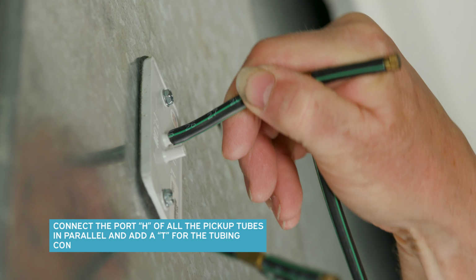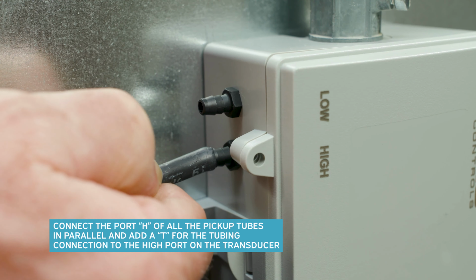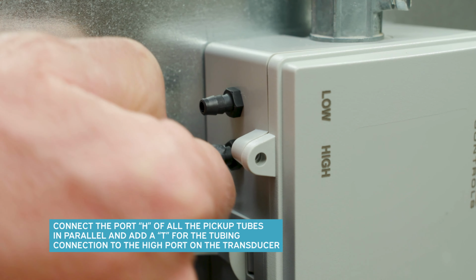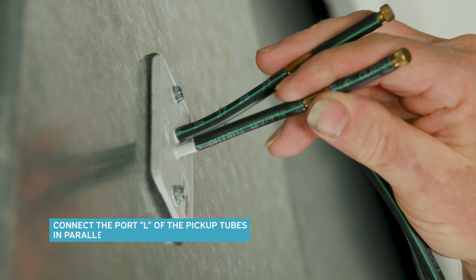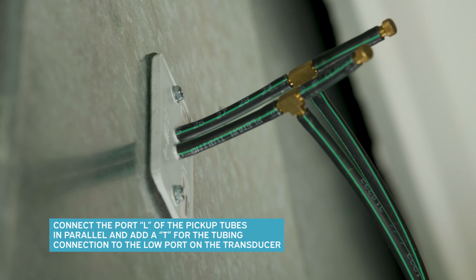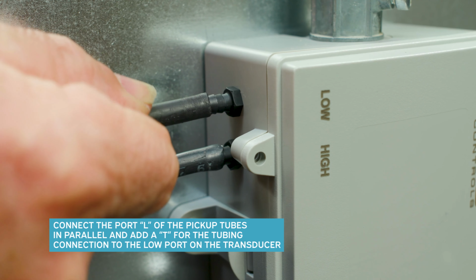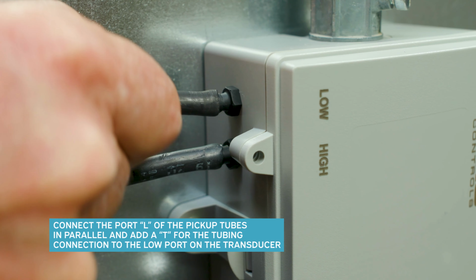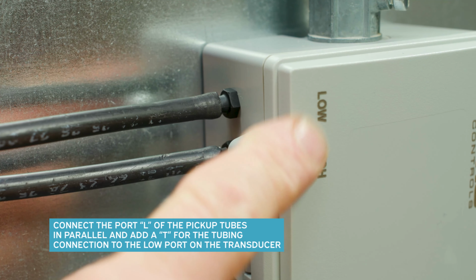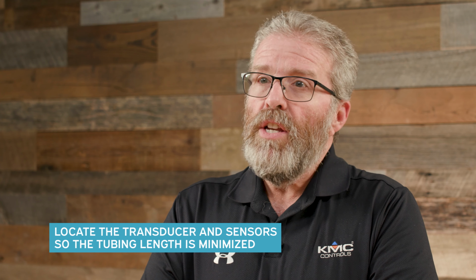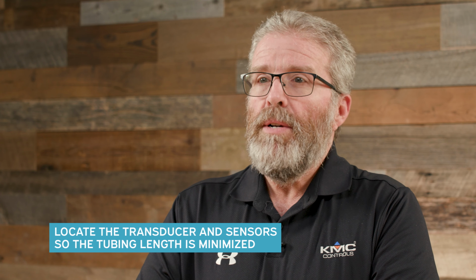Now that the transducer is installed, connect the port H's of all the pickup tubes in parallel and add a T for tubing connection to the high port on a supply air pressure transducer. It is best practice to locate this T in the middle of the manifold. Next, connect the port L's of all the pickup tubes in parallel and add a T for the tubing connection to the low port on the supply air pressure transducer. And it is best practice to locate this T in the middle of the manifold. Again, it is a good practice to have equal tubing lengths between the high and low tubing runs. Also, locate this transducer and sensors so tubing length is minimized.